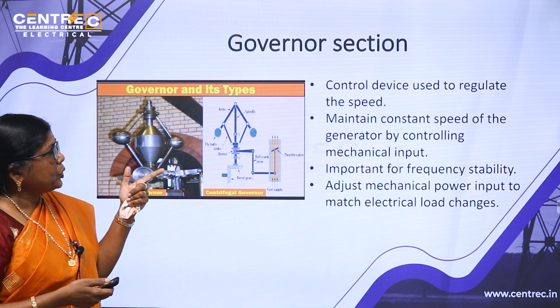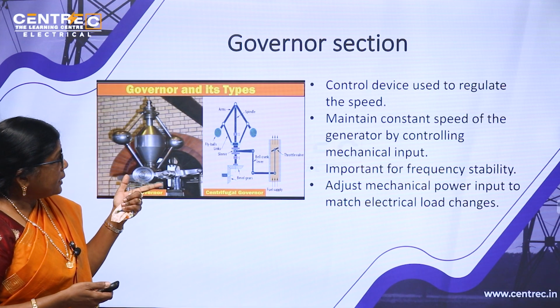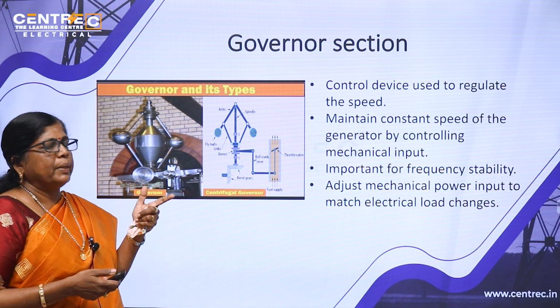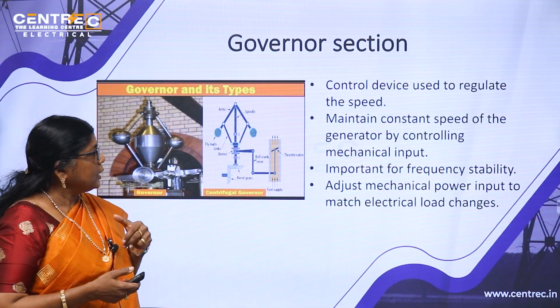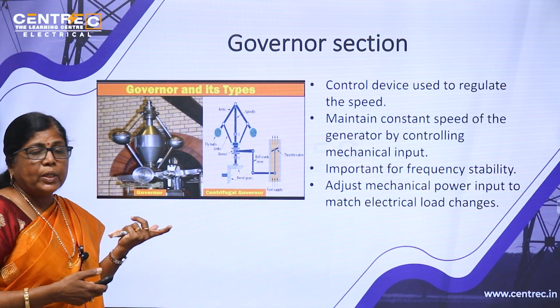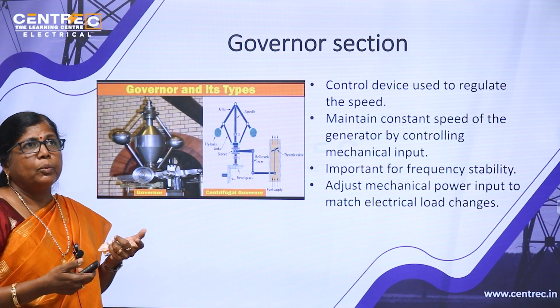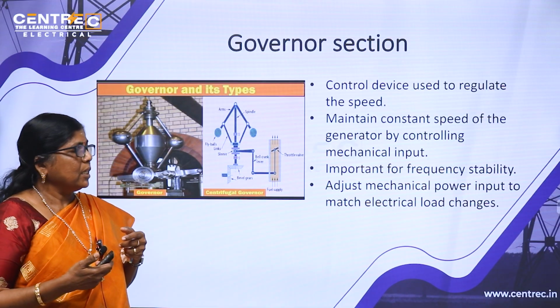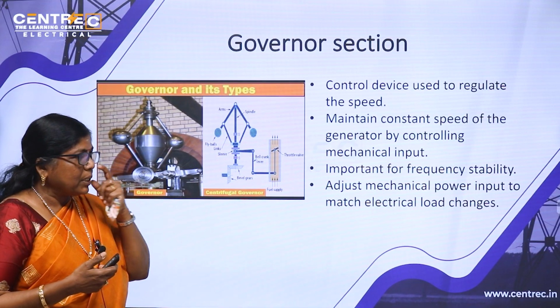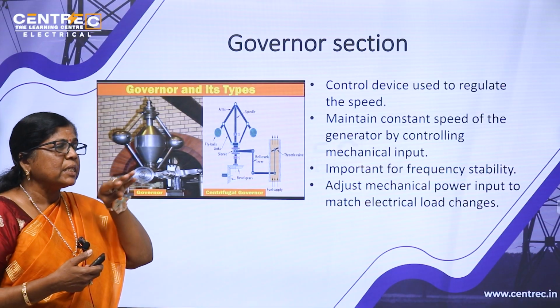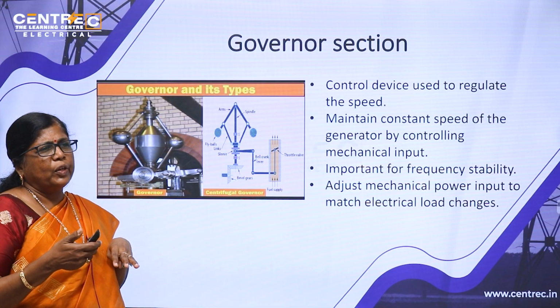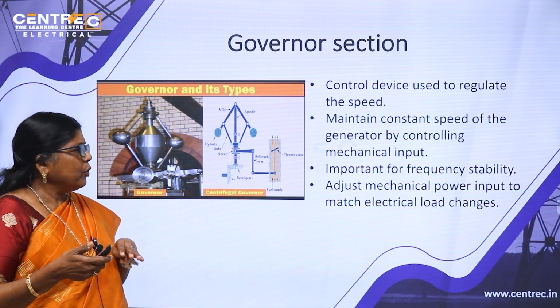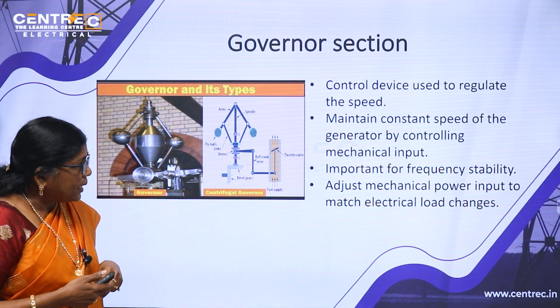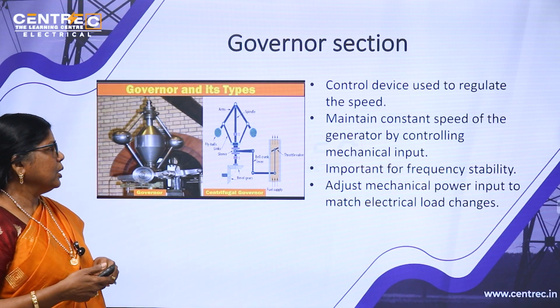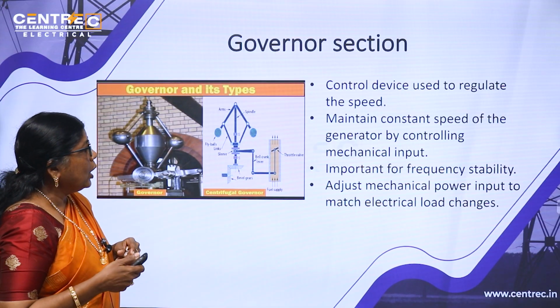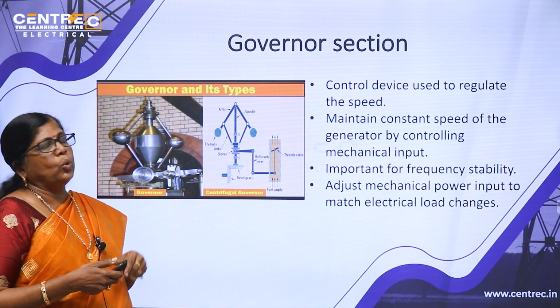So it is a control device used to regulate the speed and maintain constant speed of the generator by controlling the mechanical input. It is also important for frequency stability. That means you have studied about the speed droop characteristics. So this is important for frequency stability, so the frequency remains between 49.5 and 50.25 etc. It adjusts the mechanical power input to match electrical load changes.